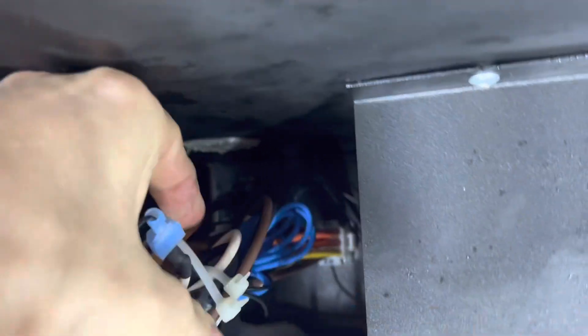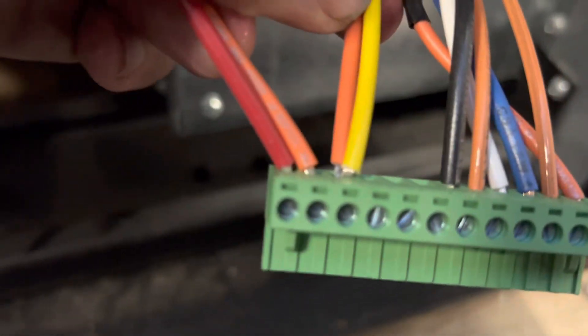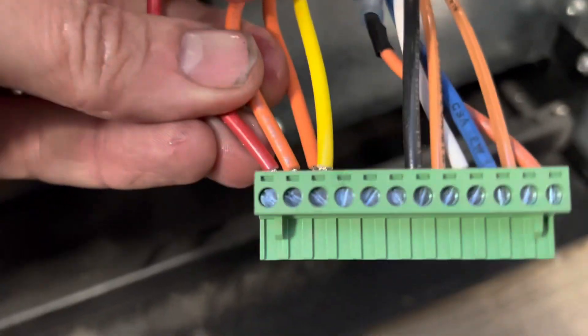That's not a jumper, which is unfortunate. The blue wires run up here. Here's a better look: your primary probe has two orange wires, and your secondary probe has a red and a yellow. You've got your orange and your yellow — one from each — those are your neutrals. So there are the wires for your control sensor and the wires for your suction sensor. I'm going to flip these two.